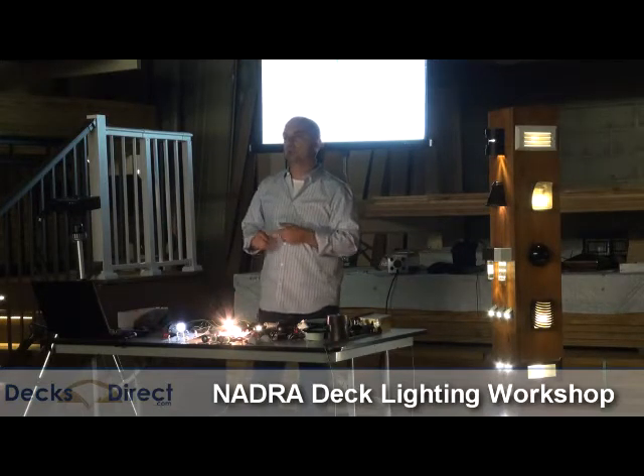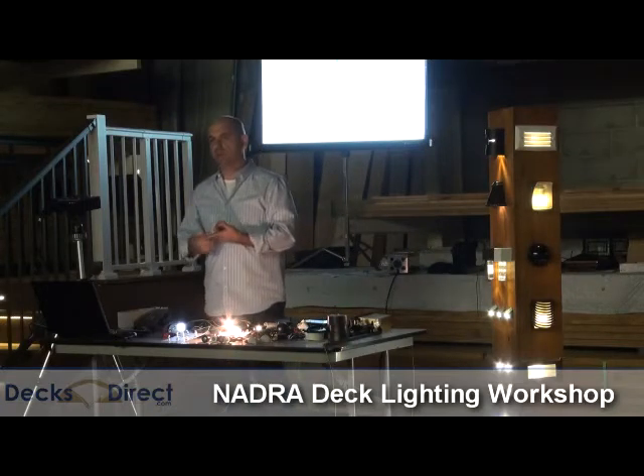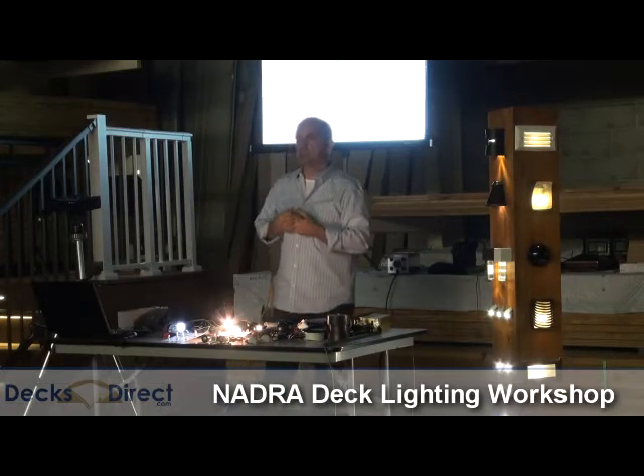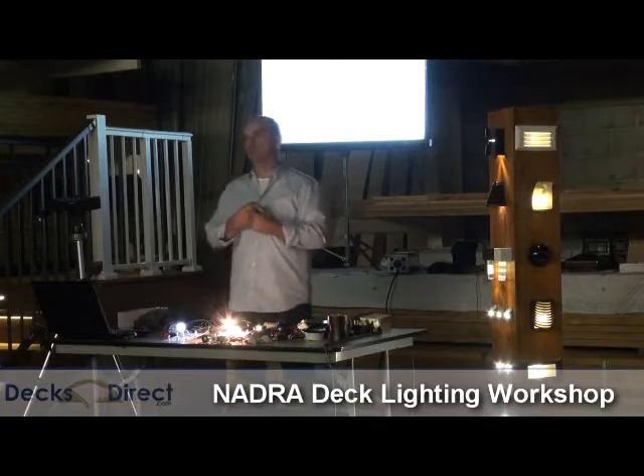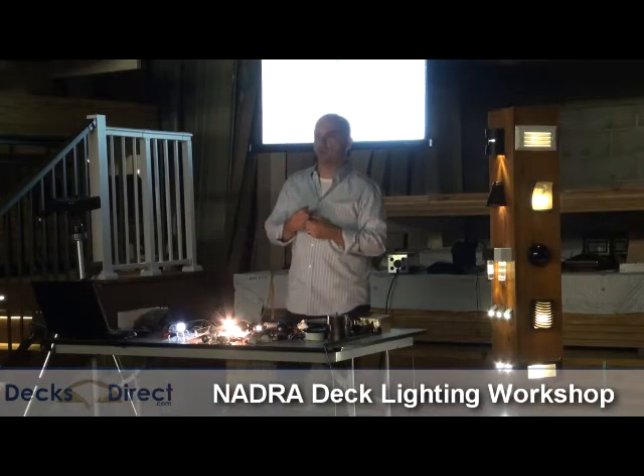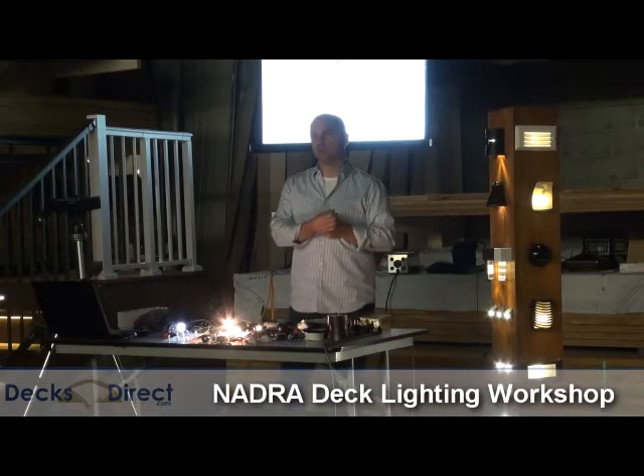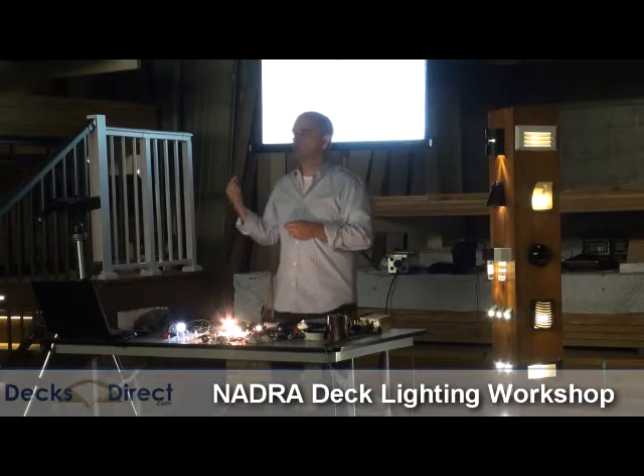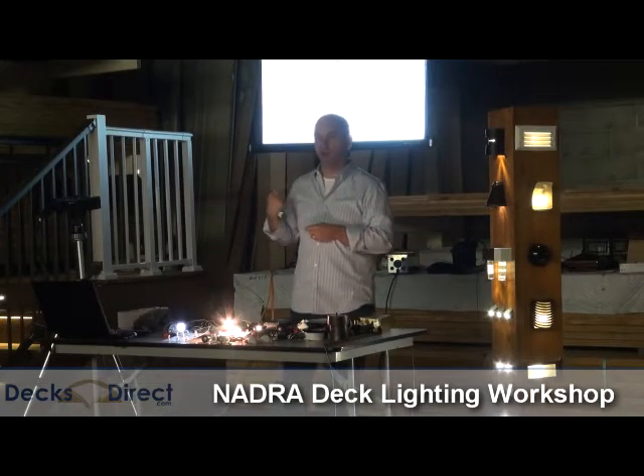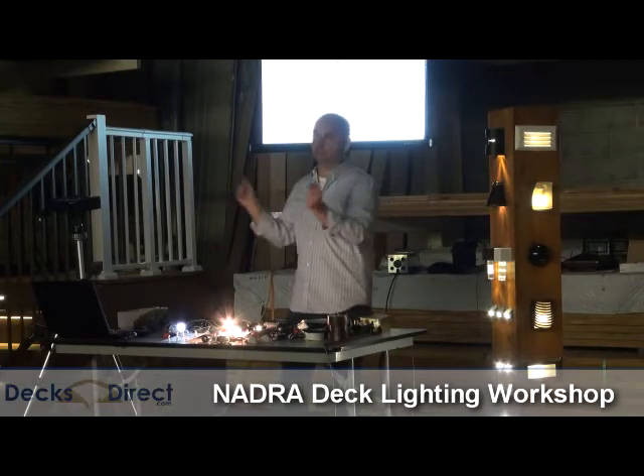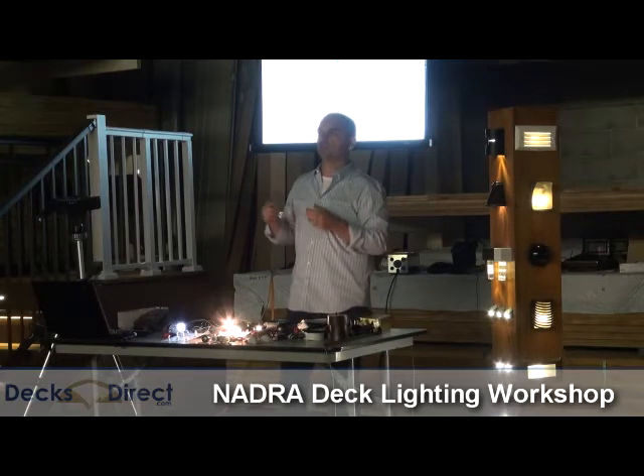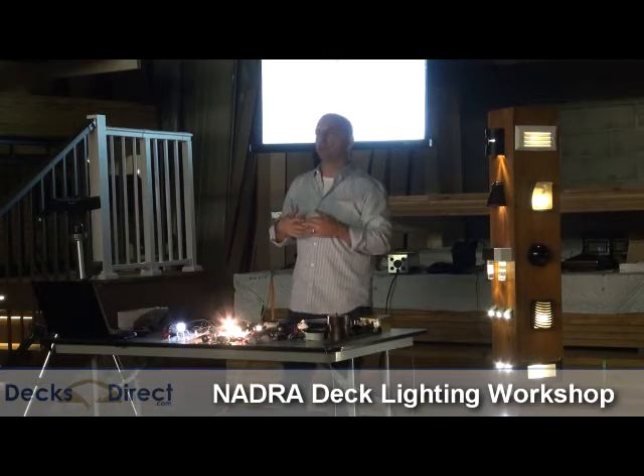That's going to be a very dim light. So a couple things you can do, the easiest, is a loop type system. When you run your line from that transformer out to your lights, from that last light, bring a line all the way back to the transformer, essentially sending power from both directions and equalizing that load.